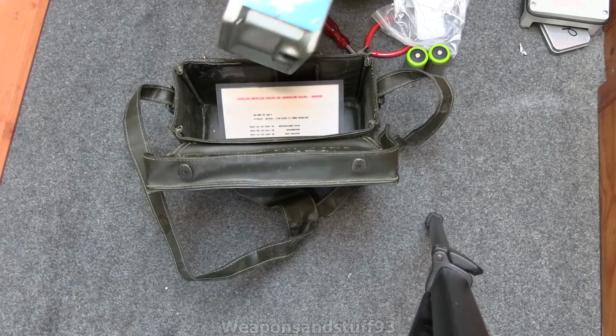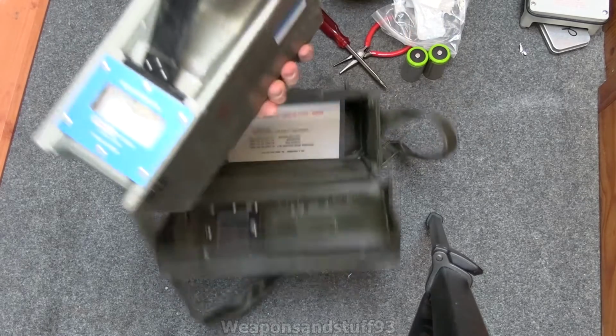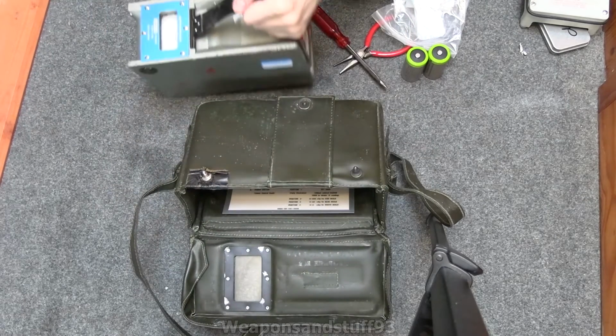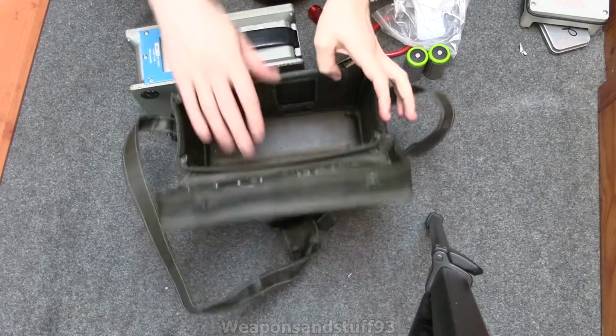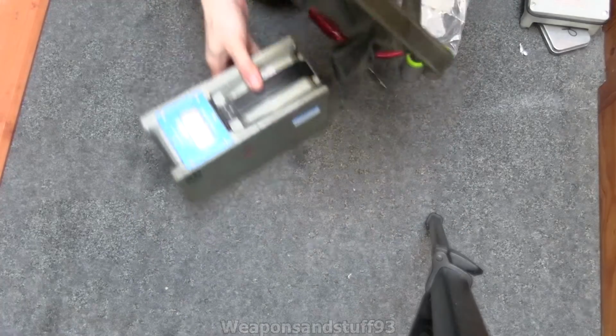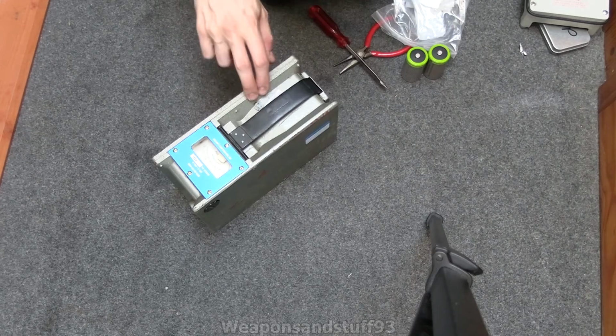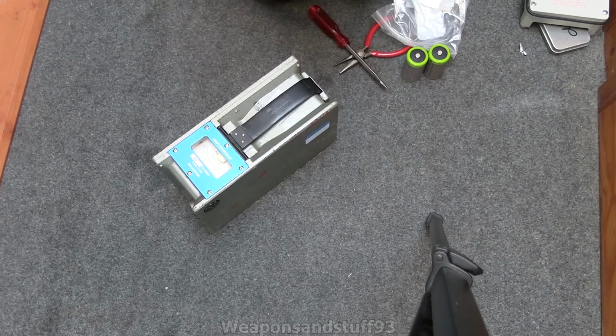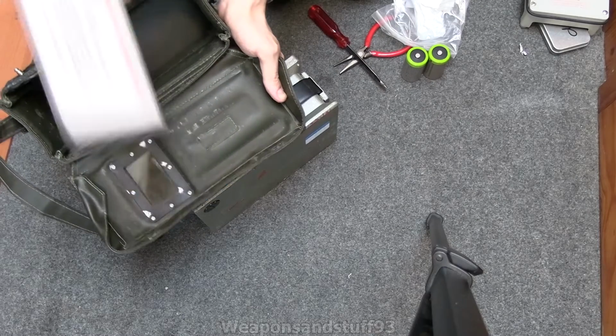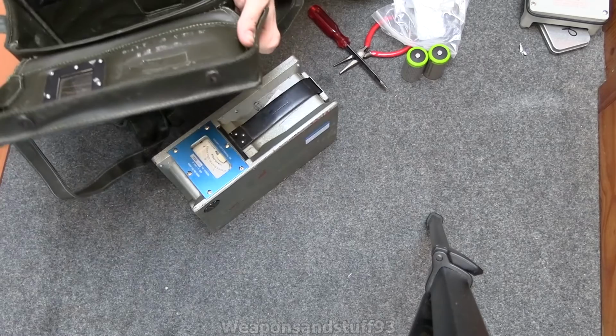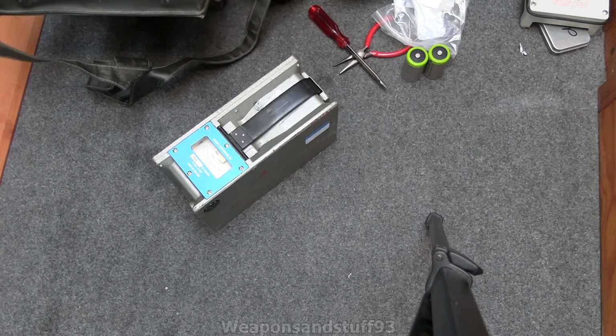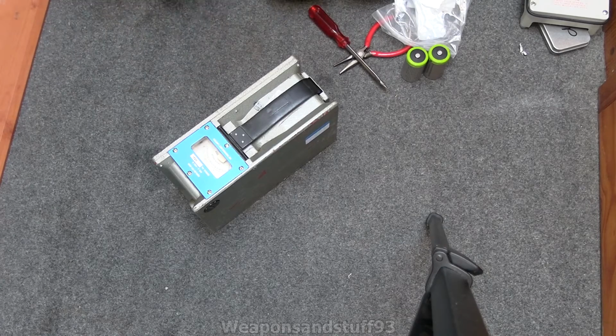So what you'll probably get when you order one is one of these that's recently been surplused, maybe with some calibration stickers on them, although in this video I'll go on about recalibrating, because when the last calibration was probably done 10 plus years ago, probably closer to 20 years ago, there's not going to be much use for that. You may get a little screwdriver in the bag there that's pretty useless. I'd say use a proper screwdriver. And you'll probably get a little instruction card. Sometimes you get the calibration documents, sometimes you don't.